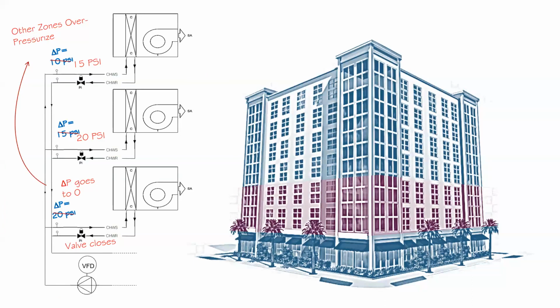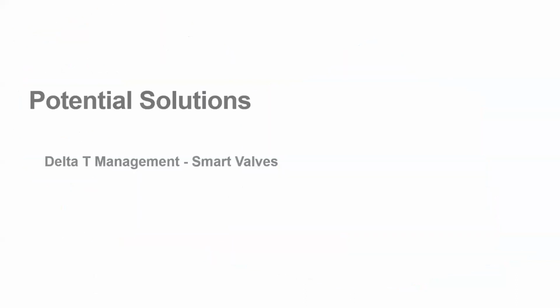The zone temperatures are stable and control to the system does not need to make any adjustments because the coil flow is unaffected. In fact, in a PI system, or a pressure independent system, since all zones are hydronically isolated, the control system only needs to respond to changes in the load, not to every little change throughout the system. So another potential solution would be a smart valve with delta T management.